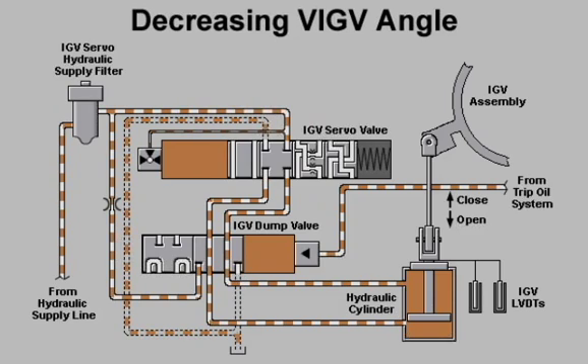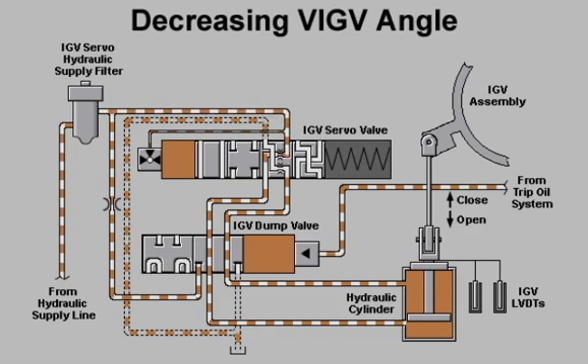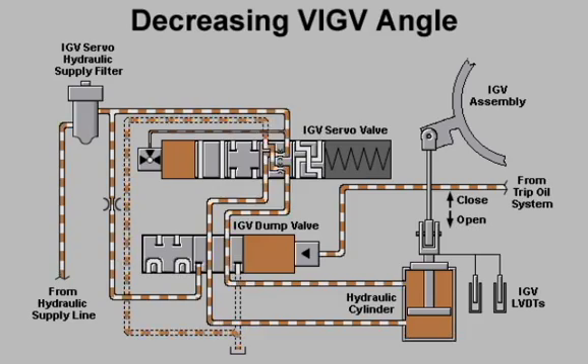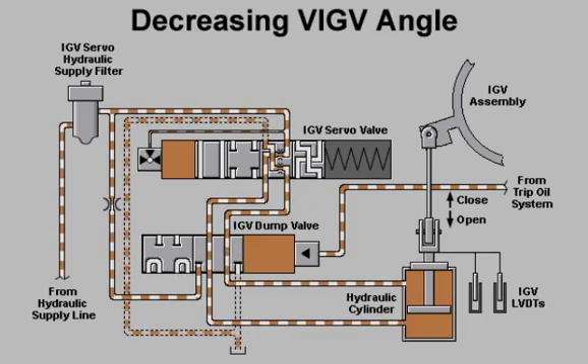If the VIGV operating sequence requires a smaller variable inlet guide vane angle, the control system will shift the spool valve of the IGV servo valve to a position which allows hydraulic fluid to flow to the lower section of the hydraulic cylinder. Hydraulic fluid from the upper section of the hydraulic cylinder is dumped to drain.